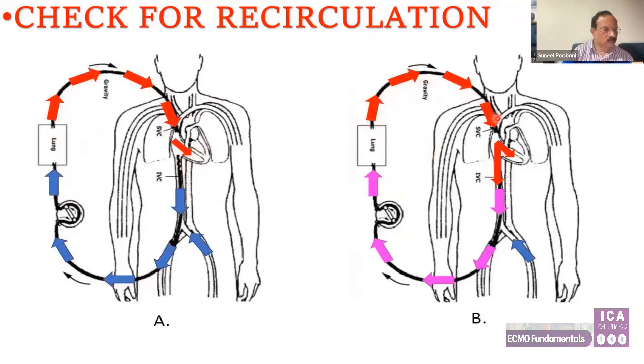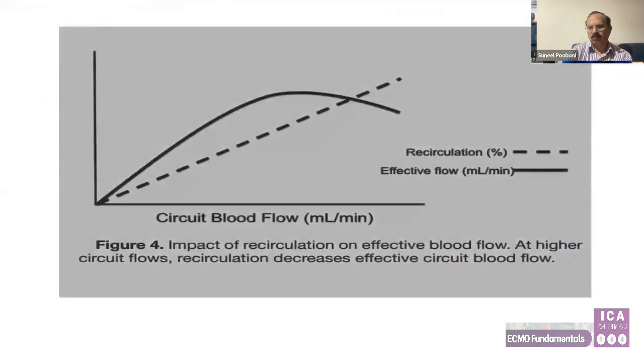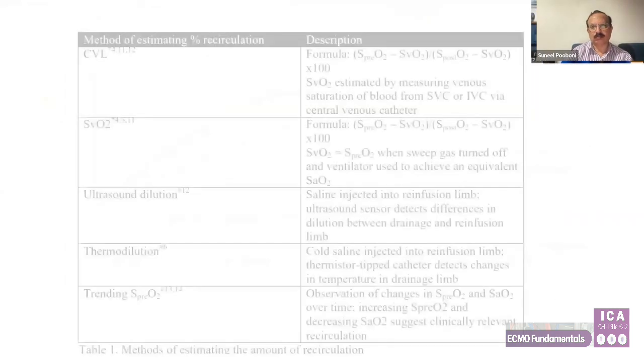But if there is recirculation, the blood goes into the left, but most of the blood might also come into the drainage cannula and it might recirculate in the system. Depending upon the degree, the percentage of recirculation, the effects start to appear. For a recirculation of 20-30%, the effects may not be seen, but if the recirculation starts rising, the effective flow which goes into the patient might be reduced, that is, the oxygen content of that flow will be reduced, so hypoxia might set in.